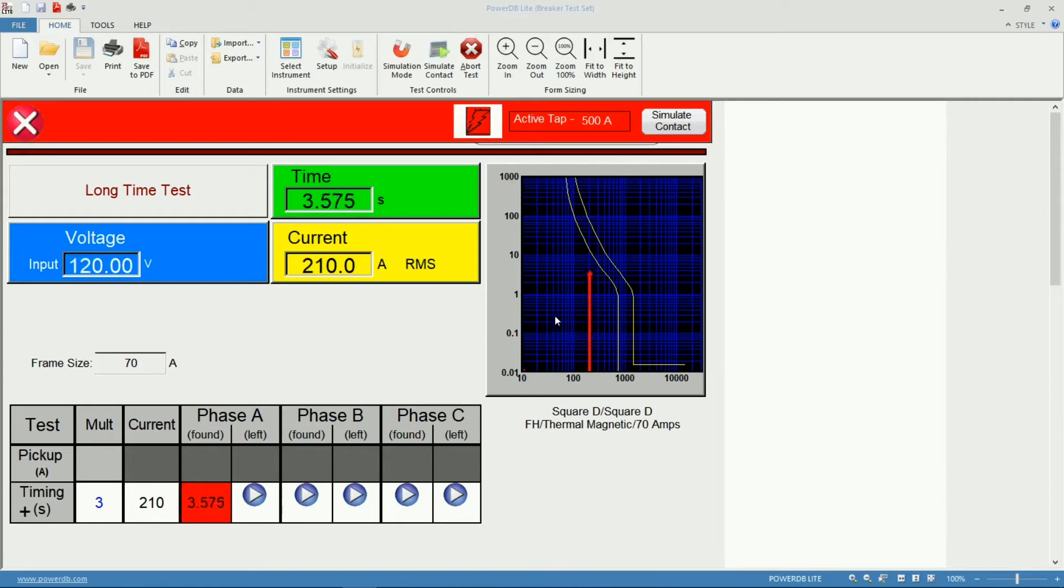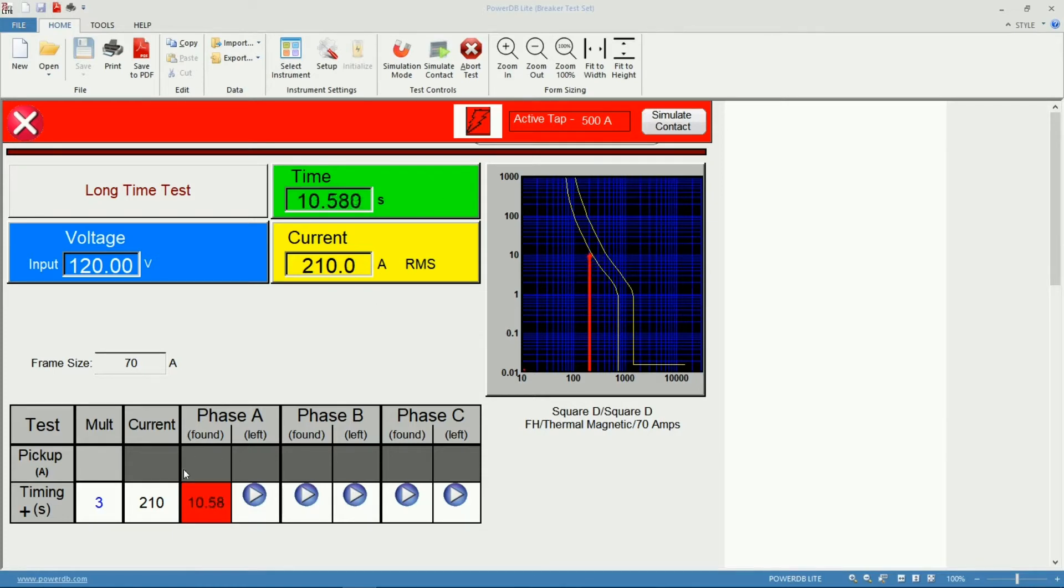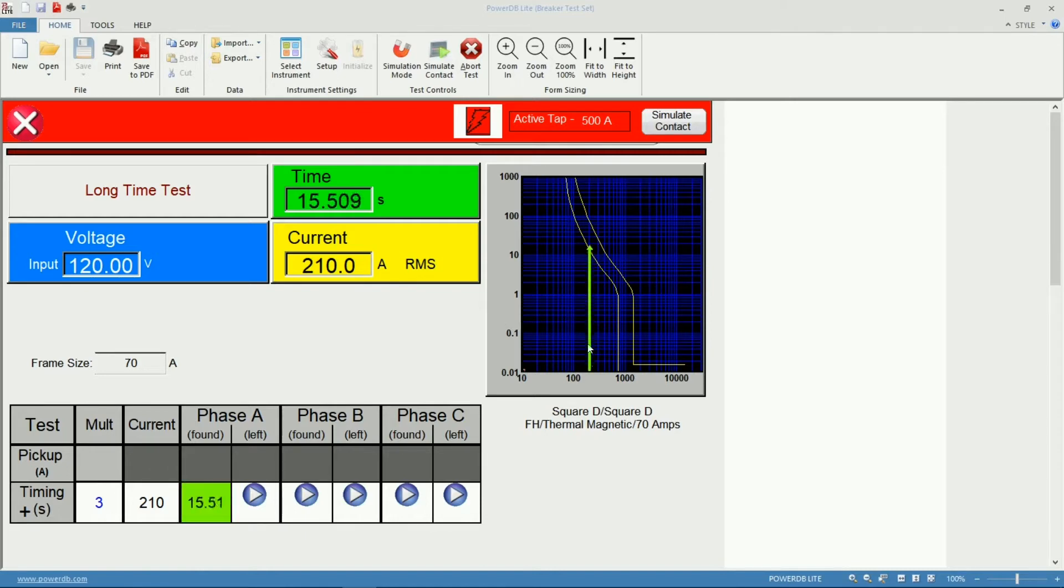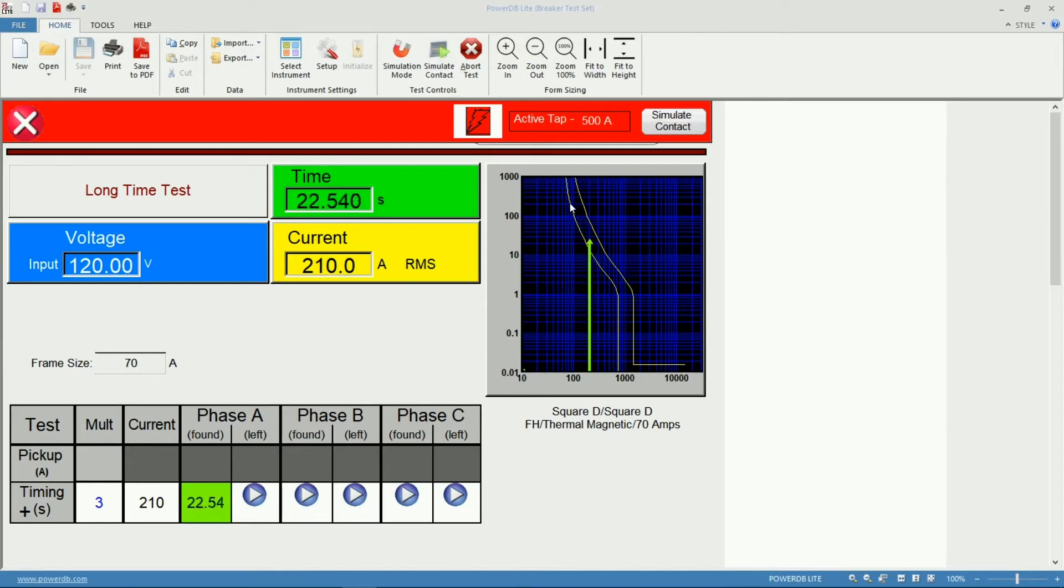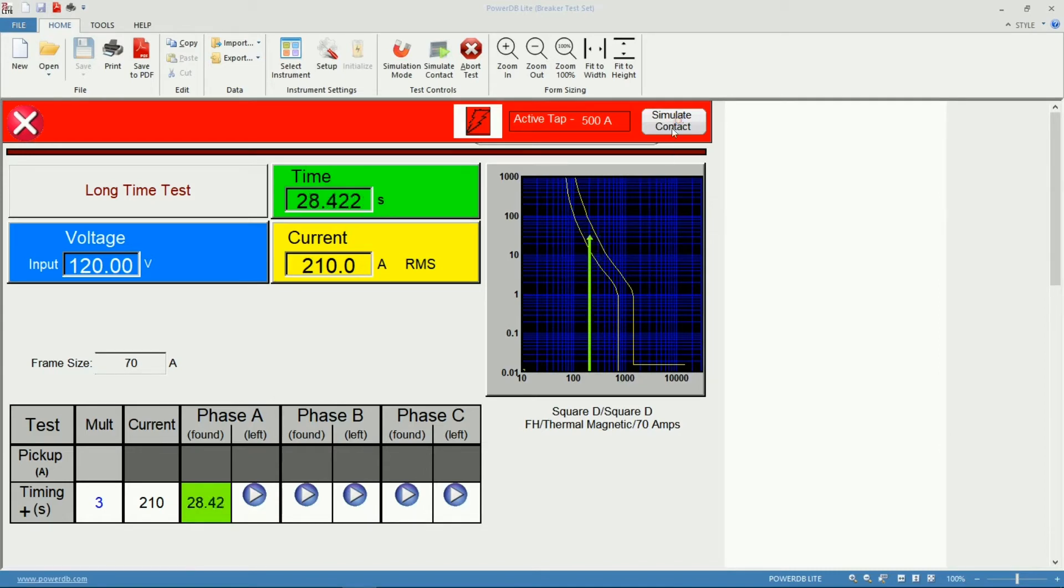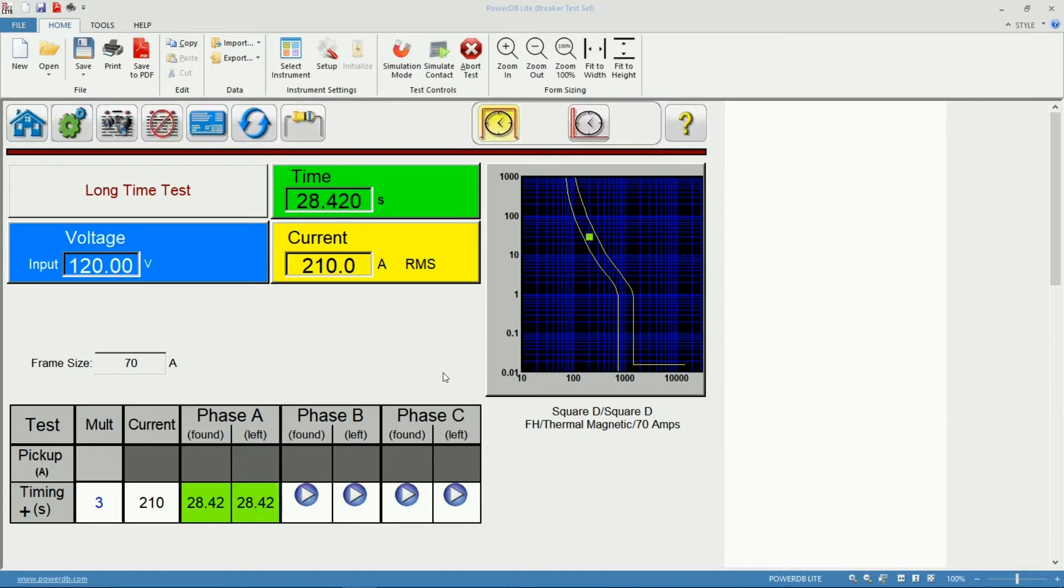Notice that I get live indications in the curve here on my timer and also time down here on Phase A. Also notice that my arrow was red because it was still outside the limits allowed or defined by this TCC and it becomes green when it goes inside the limits of the curve. I'm going to simulate a trip right there, and both of my measurements are green here.